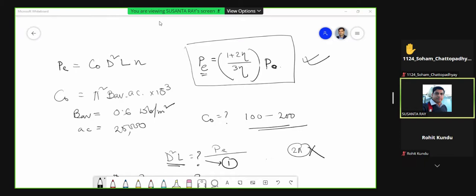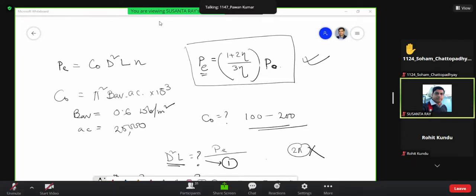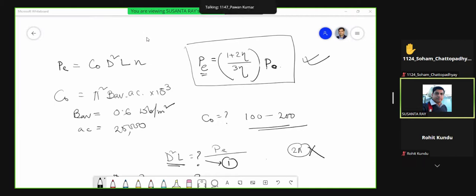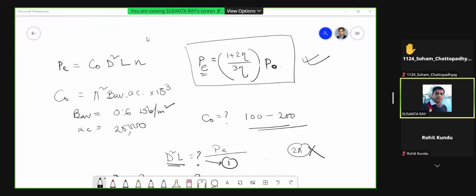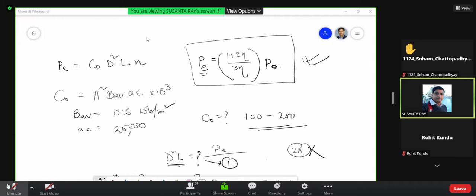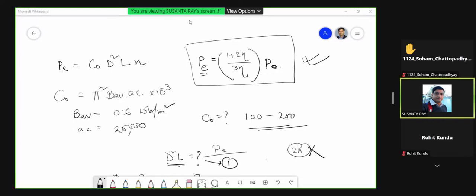Okay, you can proceed with that. Okay. Sir, what about mine? Means that dimension was correct, 313.93 and 328.75. No, it's okay, but it is on the lower side actually. I think you have assumed more flux density. Yes, sir, the maximum one. I thought power rating is high, so I should assume 0.6. What was your power rating? 110, no? Yes, sir. Okay, you can proceed with that.